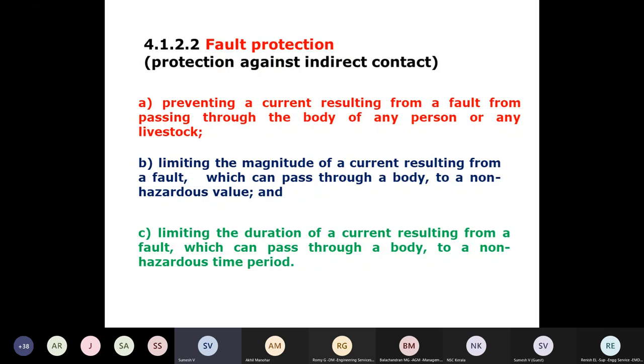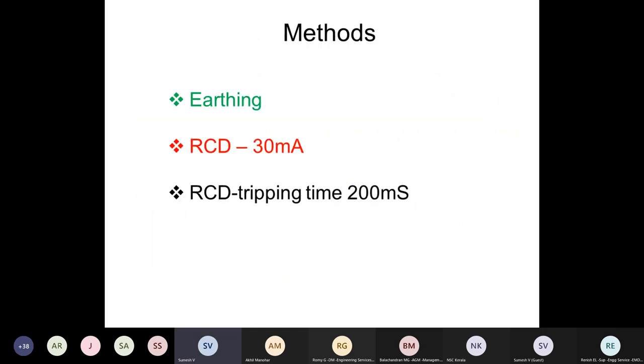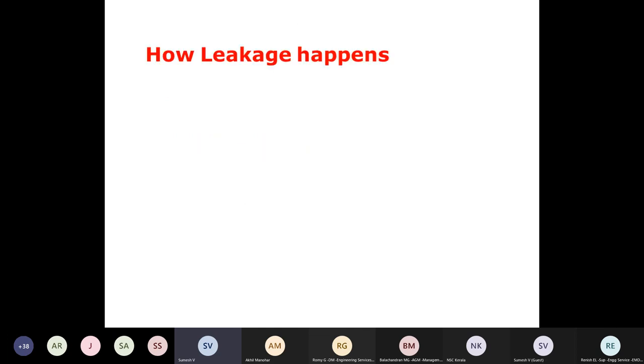For that, we are using different techniques. One is earthing. Earthing we have already discussed. The second thing is RCD, residual current device. A residual current device is to limit the leakage to a certain milliampere. In domestic premises, it is recommended to use RCDs of 30 milliampere sensitivity, and the tripping time of a 30 milliampere RCCB used in domestic premises should be less than or equal to 200 milliseconds.